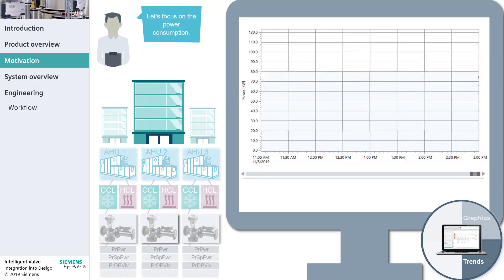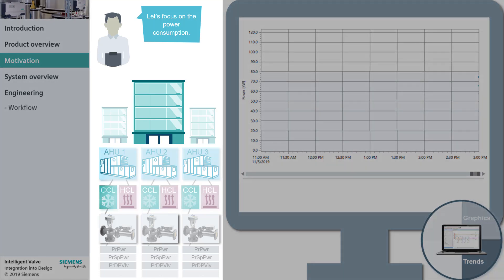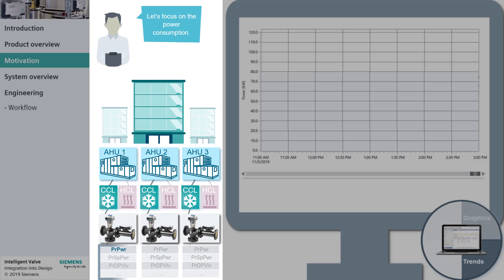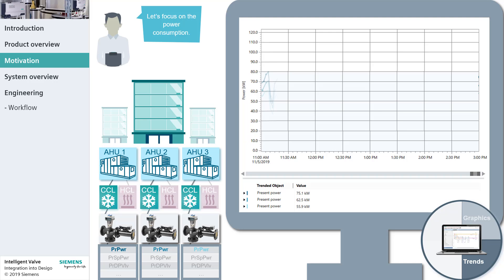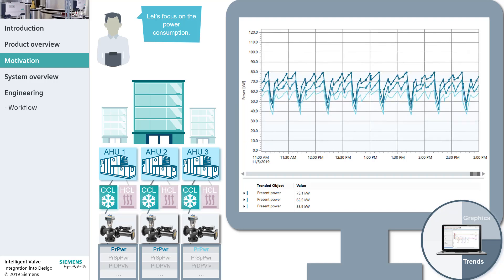Mike is not limited to trending data from one intelligent valve. As a second option, he can analyze data point curves from multiple valves at the same time. Mike is interested in optimizing the thermal power consumption. At a glance, he can identify any deviations from the expected power values. In the time period, the power consumption seems to be in the normal range.